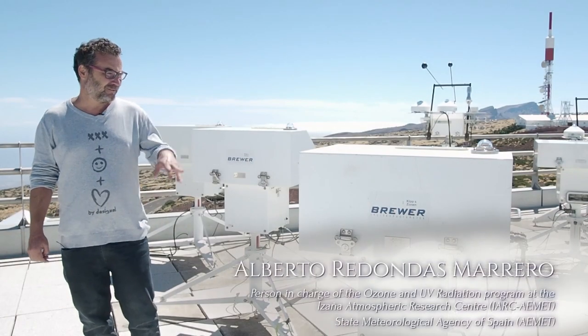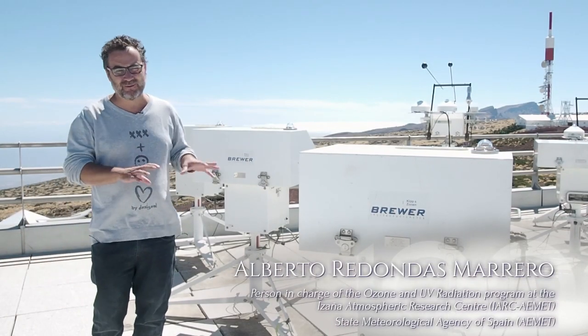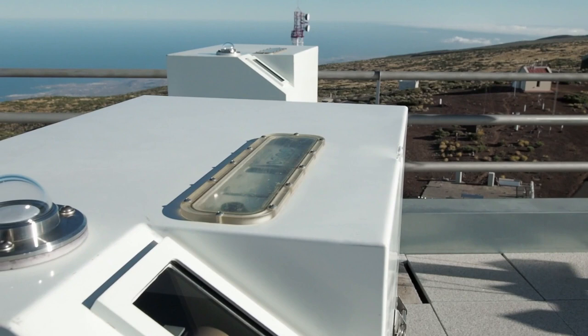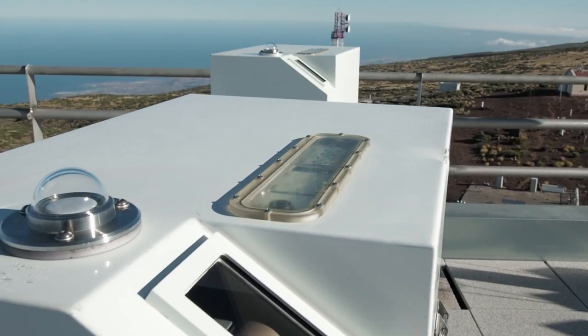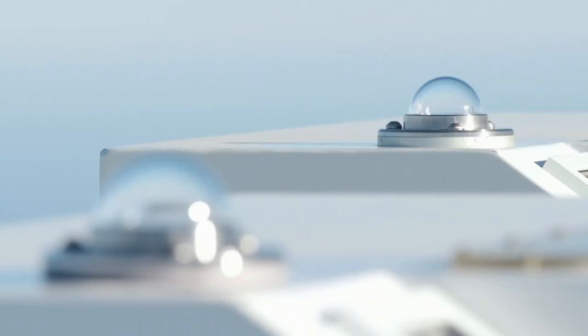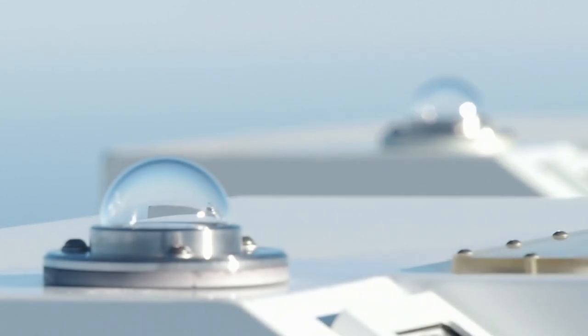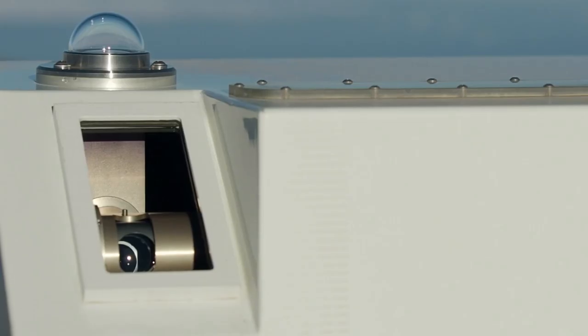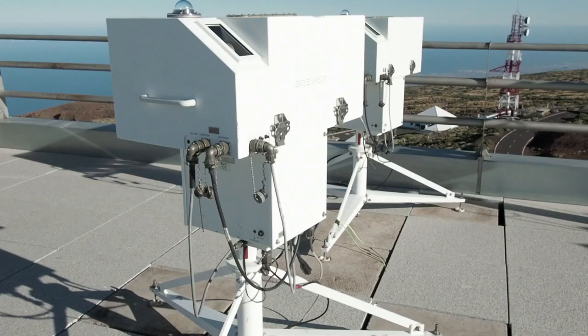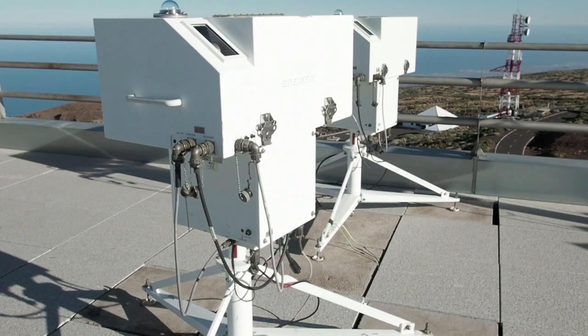The Brewer is a device designed to measure ozone, but it does so by measuring ultraviolet radiation, and therefore also provides measurements of ultraviolet spectral radiation, which means we can establish vertical ozone profiles. With this equipment, we have recently been developing aerosol measurements in the ultraviolet range.